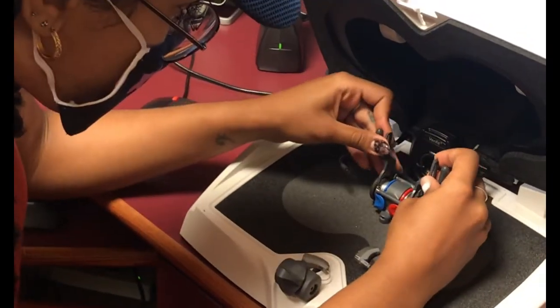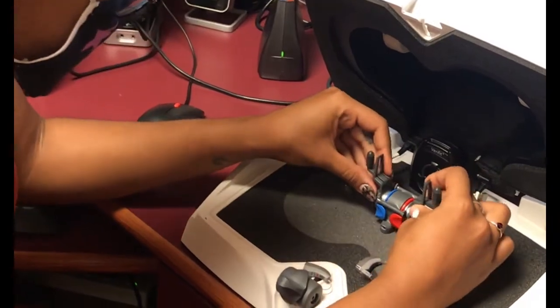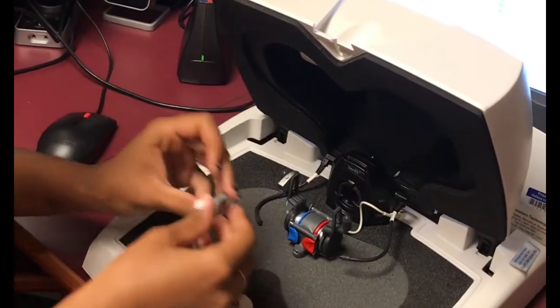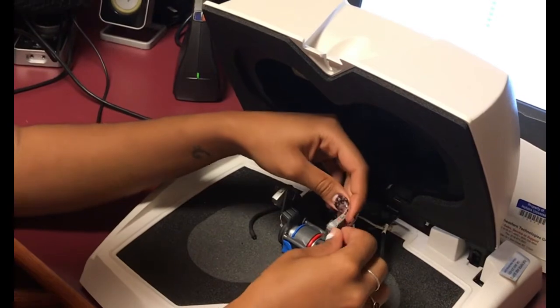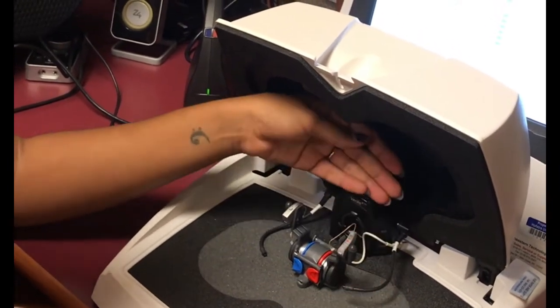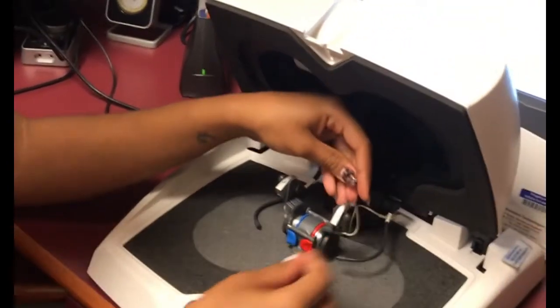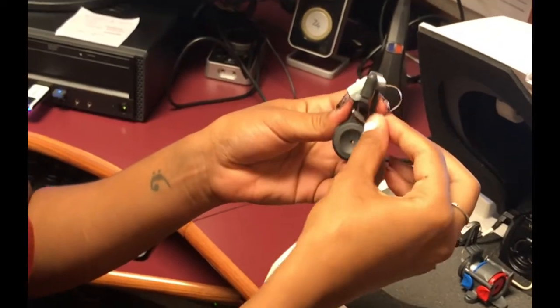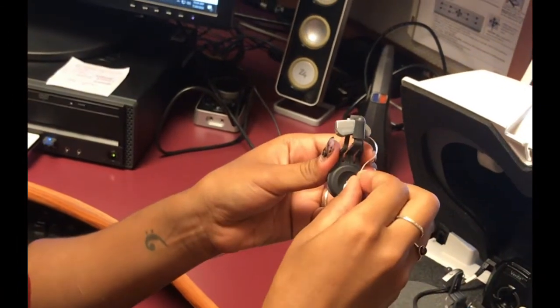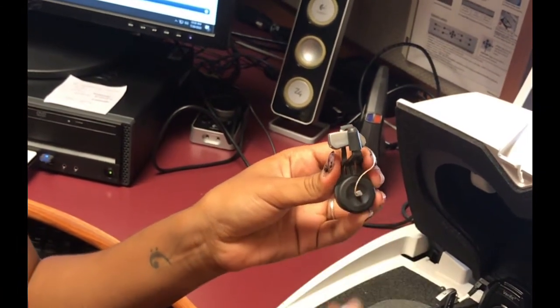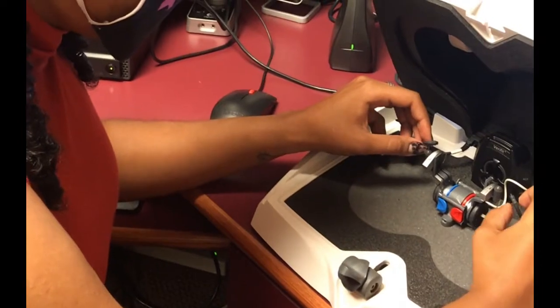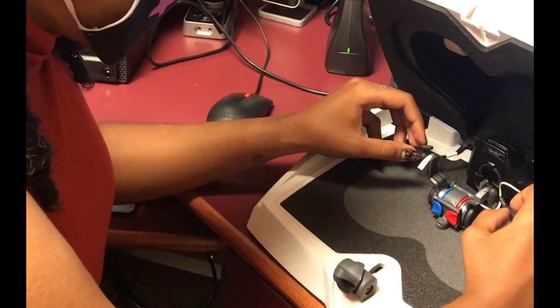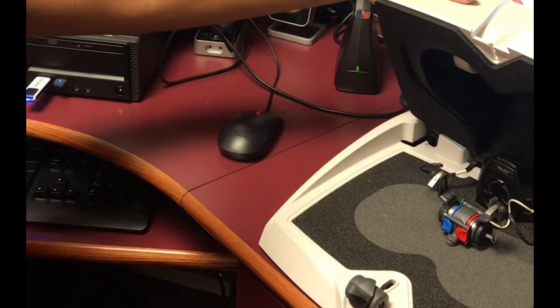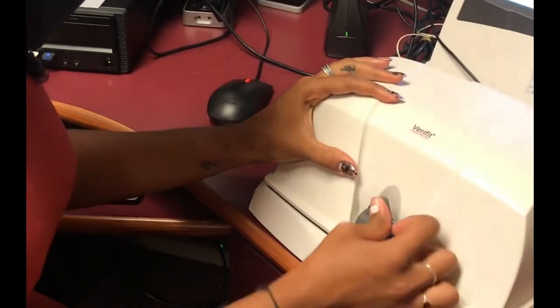And here I am just assembling everything together, starting with the clips that hold the hearing aid. The left hearing aid is on, and I'm just showing you the right hearing aid. This is not proper placement. You have to turn the hearing aid around, sit it snug, and the receiver of the hearing aid goes into the small hole of the adapter that leads into the coupler. And lastly, you fix the reference microphones so that they are close to the microphones of both hearing aids. Close the test box and you're ready to start your test. And this is just a close-up of the assembly.